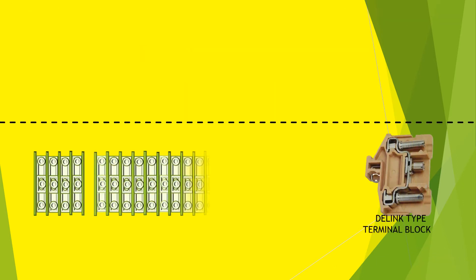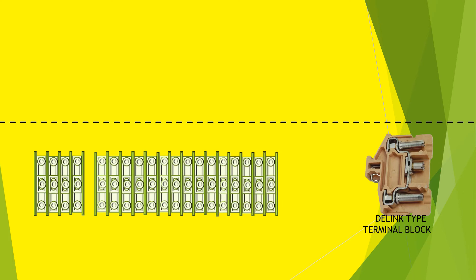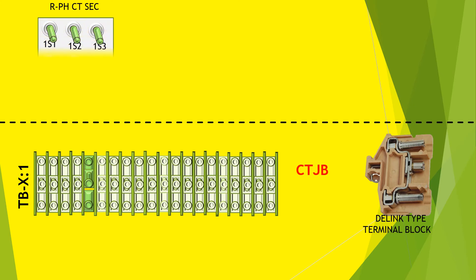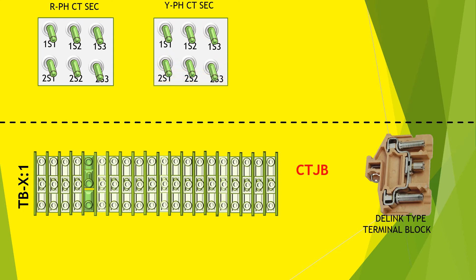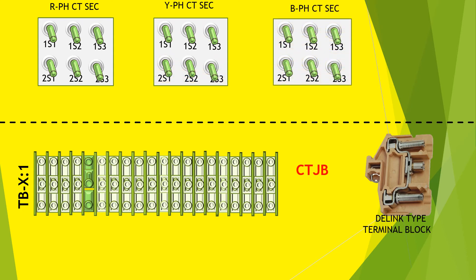These are delink type terminal blocks generally used for CT connection in a CT junction box. If required, the connection of terminal wires can be achieved by this terminal block. Images of two-core, three-terminal CT secondary leads — 1S1, 1S2, 1S3 and 2S1, 2S2, 2S3 — of R-phase, Y-phase, and B-phase CTs are drawn here.